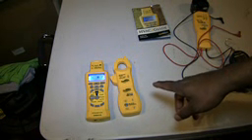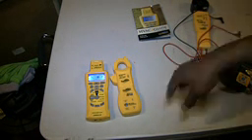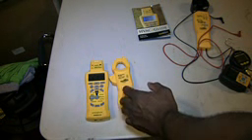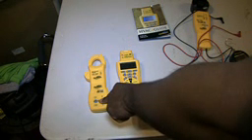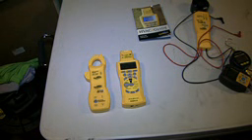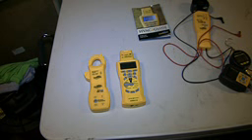So I'm not sure whether it's a delay issue or there's something special I have to do with the transmitter versus having the AC clamp head on top of the HVAC Guide itself. Now, the cool thing is, if I want to verify the amperage on a blower motor while the blower door is closed, because naturally when we check for amperage the blower door is open, and obviously we can't close the blower door and read the amperage of a blower motor, this is a very nice thing to have.